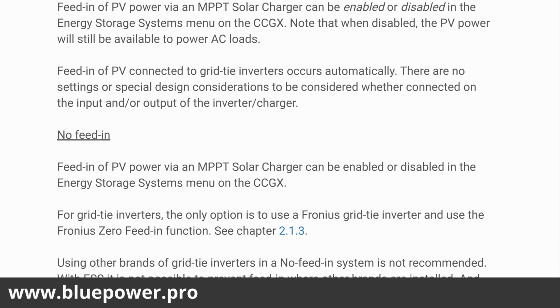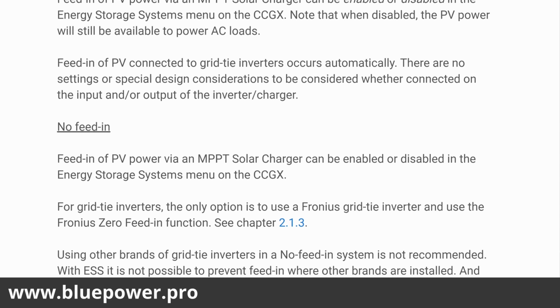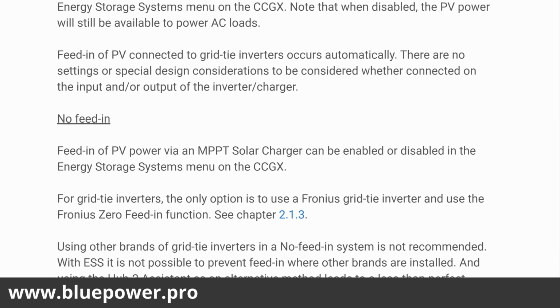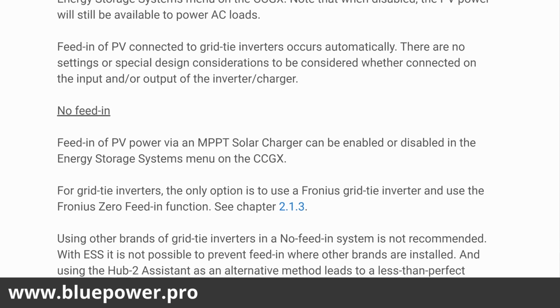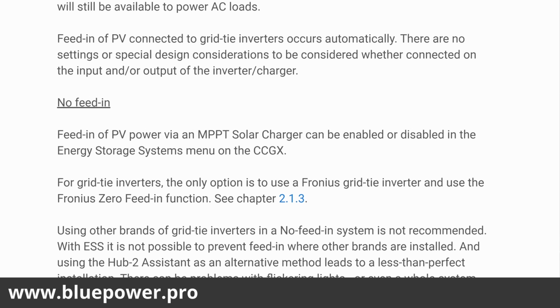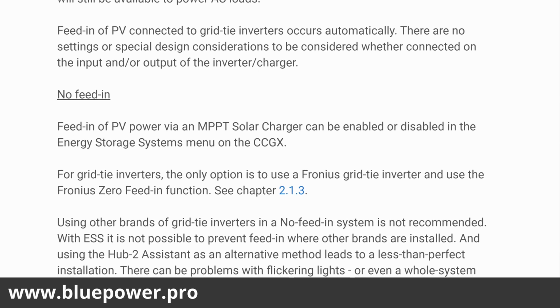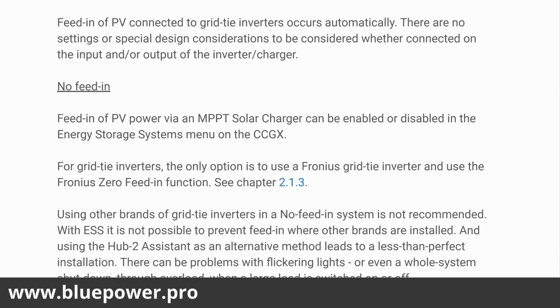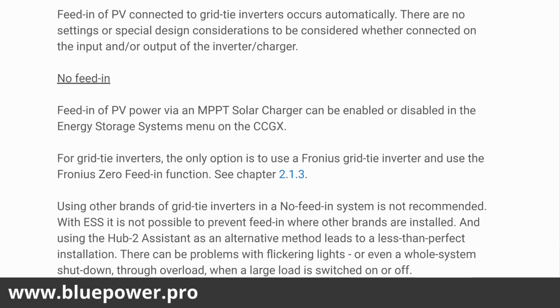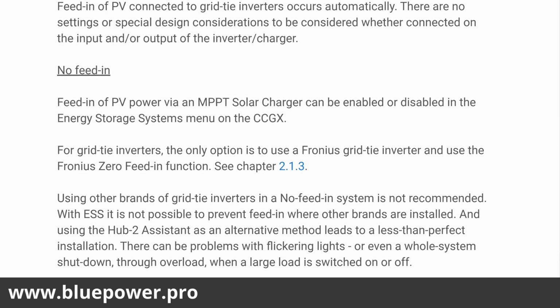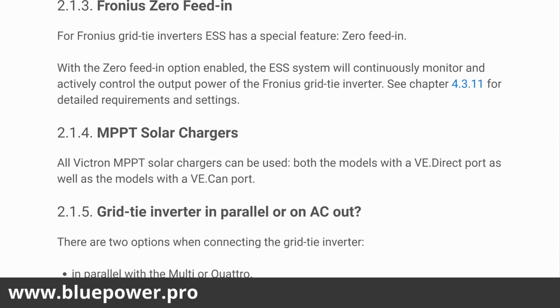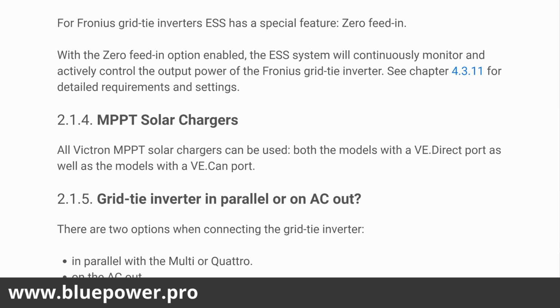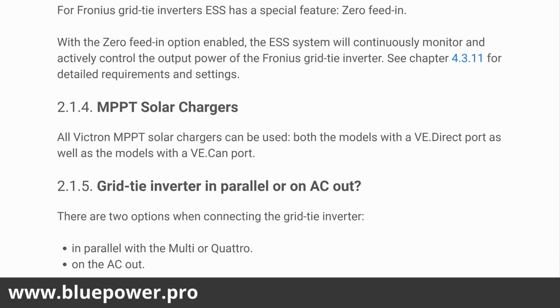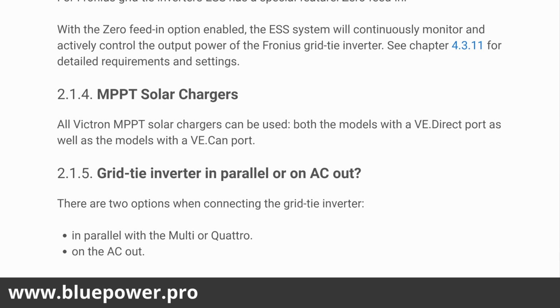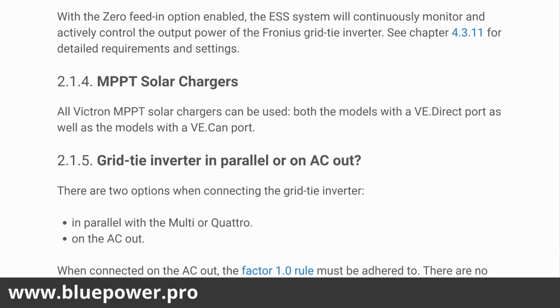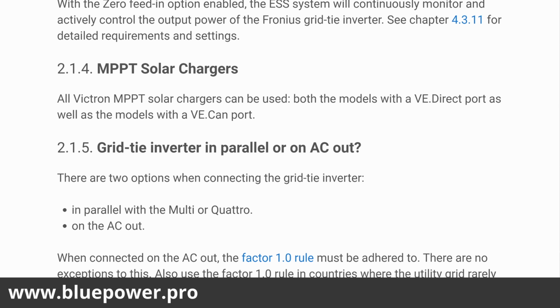You can also, if you've got a Fronius connected, select to feed in all its excess PV power into the grid, and also set the limit. If you've got both, you can set the limit to the maximum amount of power to feed into the grid at any given time. So Fronius zero feed-in, that's achieved by setting up the Fronius correctly as well, and then just pairing the Fronius with the Color Control GX and setting it up on the Color Control or the GX device.